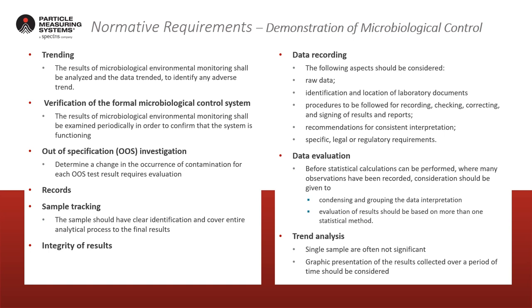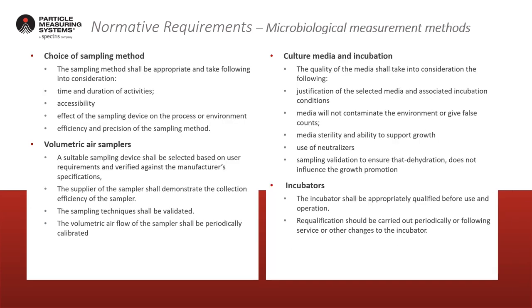The evaluation of results should be based on more than one statistical method, as data manifests itself in different ways. This is why trend analysis is important — single samples are often not significant outliers on their own, and graphical representation of results collected over a period of time must be considered. The choice of sampling method should be appropriate, with volumetric air samplers selected based upon user requirements.